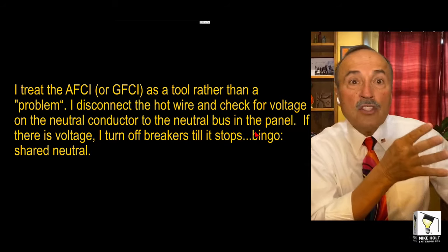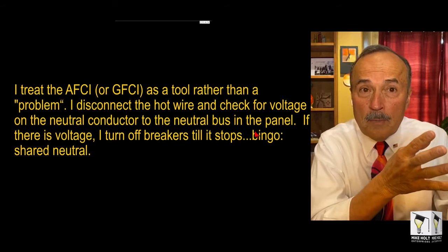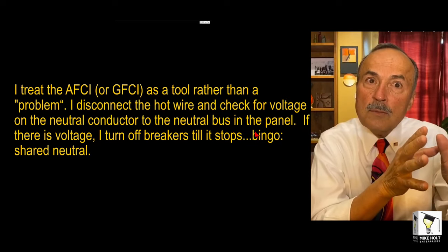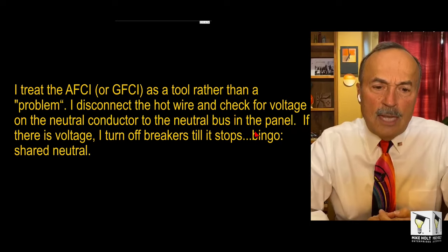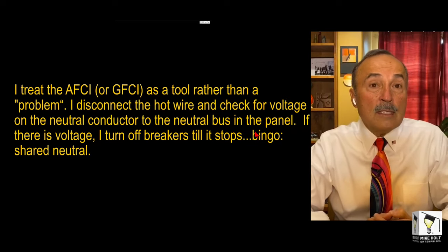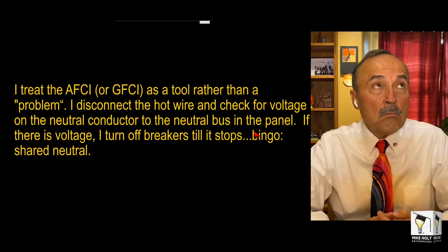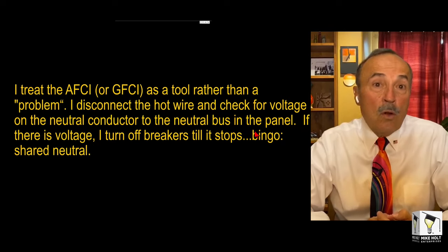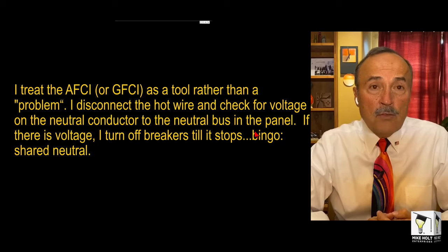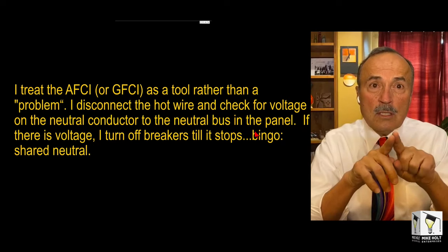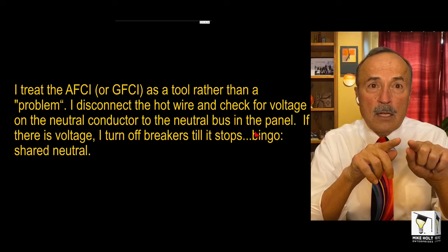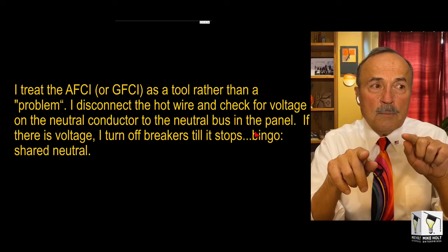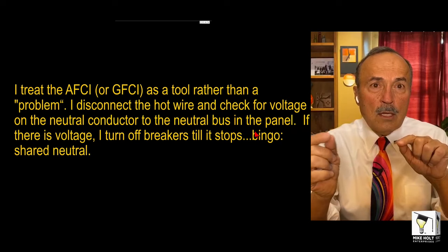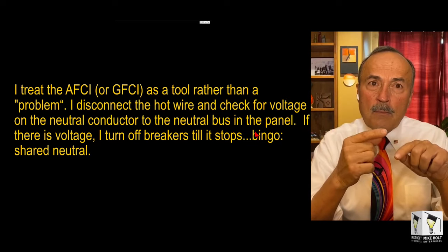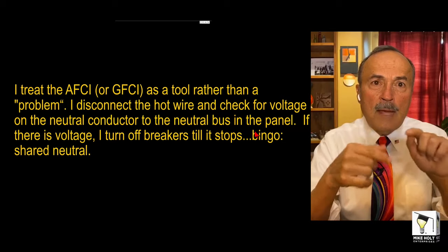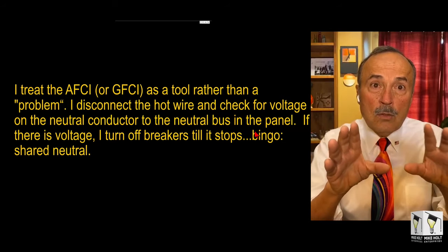So I need you to have the understanding of how multi-wire circuits operate. Here's what he said in his email, and this is what caused me some concern. He says, I treat the AFCI or GFCI as a tool rather than as a problem. Okay, I agree. You put dual function or GFCIs or AFCIs, and if there's any miswiring, the way the electronics are designed is they don't expect any neutral to ground connections. They don't expect your neutral and your equipment grounding conductor connecting. They expect current to go out on the hot, coming back on the neutral, not traveling on any other path. So it's a great device as a tool.